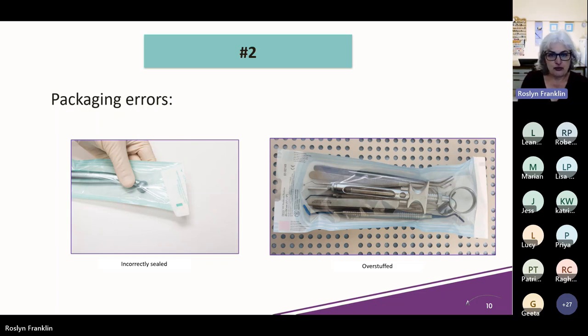Improperly sealing the bags can actually compromise the sterility, as shown in the photo on the left. You can see it hasn't been folded properly. There's a perforated line where you seal it, so when you fold it over, it's perfectly half on the paper and half on the plastic, and seals properly, keeping it sterile.